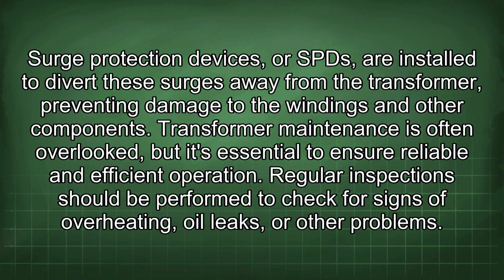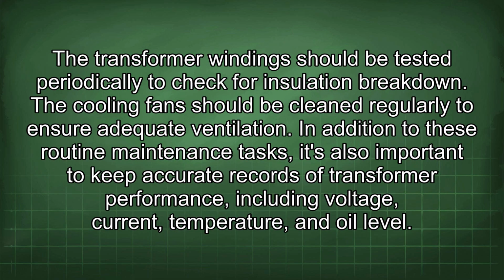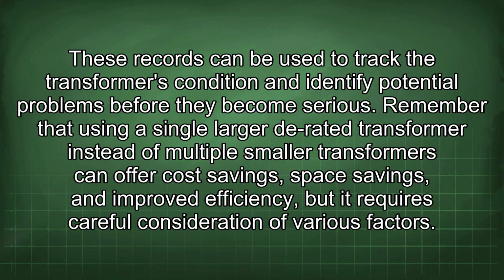Regular inspections should be performed to check for signs of overheating, oil leaks, or other problems. The transformer winding should be tested periodically to check for insulation breakdown. The cooling fan should be cleaned regularly to ensure adequate ventilation. In addition to these routine maintenance tasks, it's also important to keep accurate records of transformer performance, including voltage, current, temperature, and oil level.